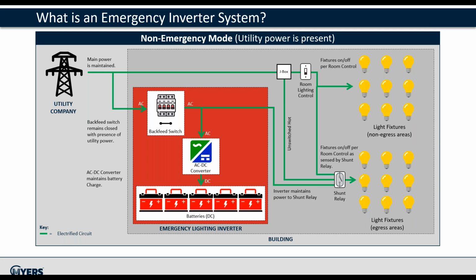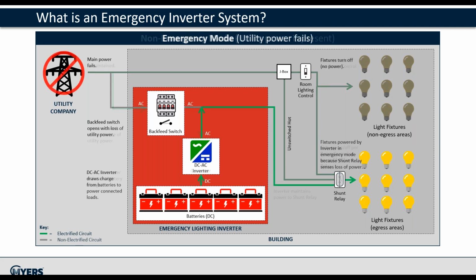During emergency operation, the utility company main power feed is lost, illustrated by the gray color in the diagram. Instantaneously, the backfeed switch opens, disconnecting the utility company from the inverter system, so no voltage is fed through to the utility grid. The power module reverses from an AC to DC converter to a DC to AC inverter, and the shunt relay closes, passing emergency power to the load, independent of the room lighting control.